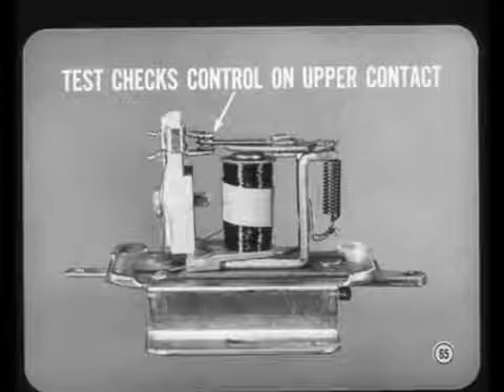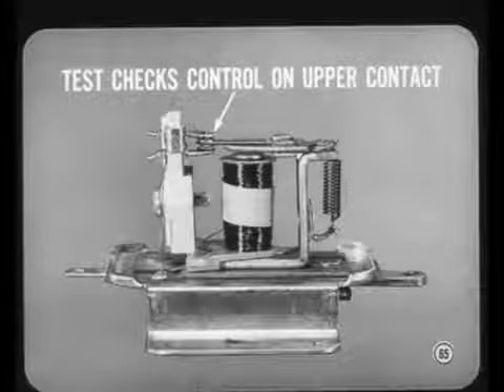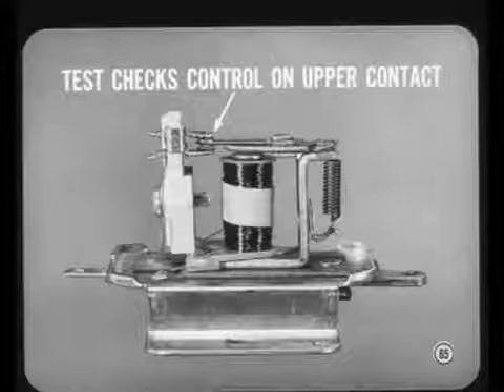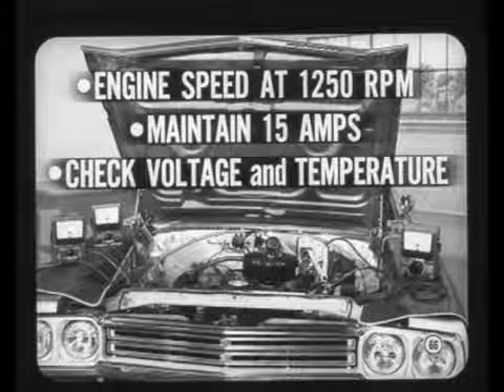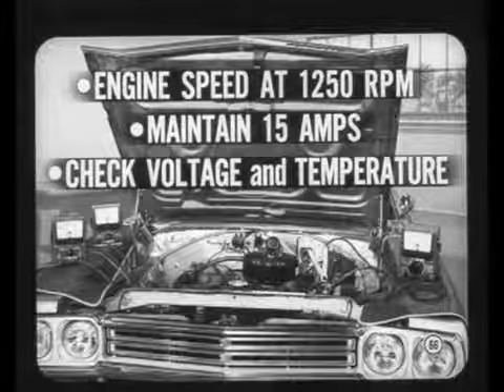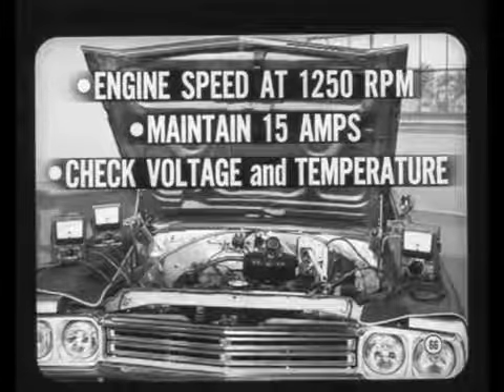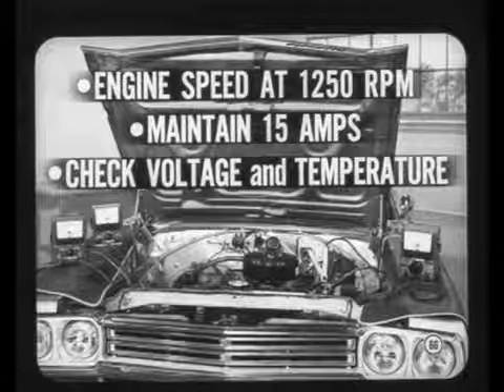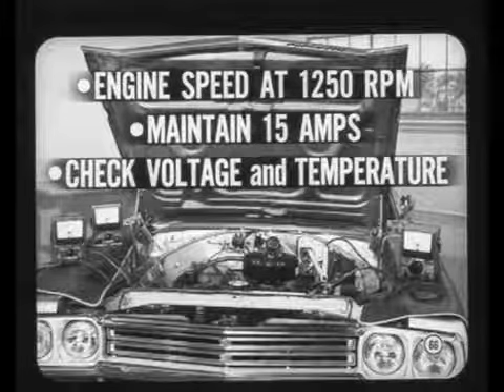Ready and waiting, Tech. The first part of the test checks voltage control with the regulator operating on the upper contact. This is the normal condition when the charging system is carrying a high electrical load at relatively low speeds. Recheck the engine speed to make sure it is at 1250 and adjust the carbon pile to maintain the specified 15 amps. Then check the voltage and regulator temperature against the specifications.